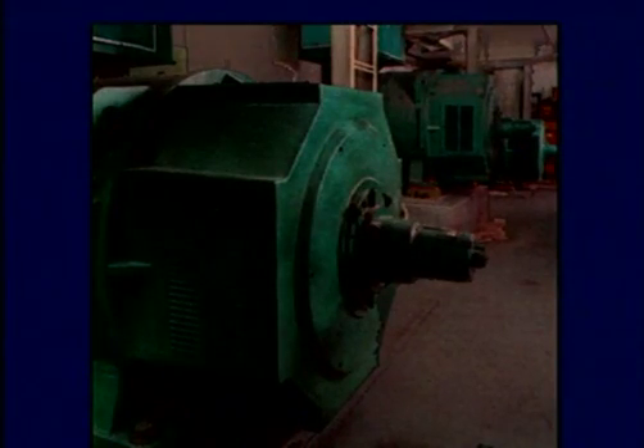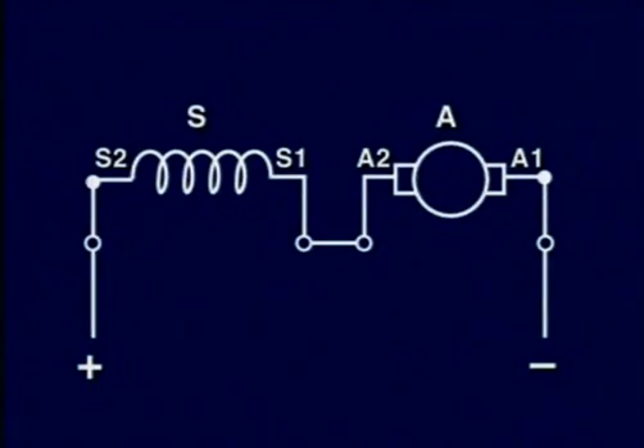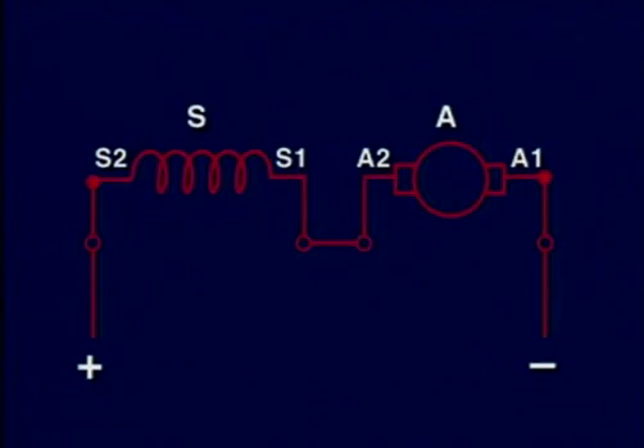The next problem that we encounter is when the motor is running and gives us signs of overheating or not being able to pull its rated load. Because the motor is running and has proper voltage at its terminals, it is pulling current, and therefore there is not an open in either of its windings.